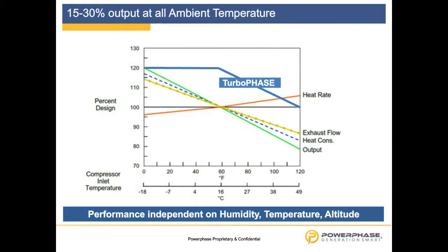And what Turbophase does is, depending on the design capacity of the gas turbine, we are adding our 5% incremental air to the compressor discharge, following the output of the gas turbine in parallel. And what is seen here, and that is supported by real-time data later as well, is that the added power on top of the gas turbine power is independent of humidity, temperature, and altitude.